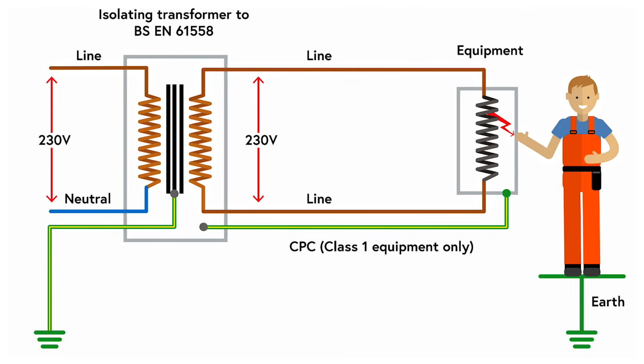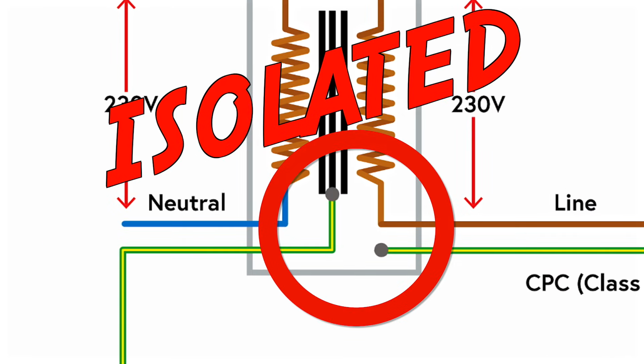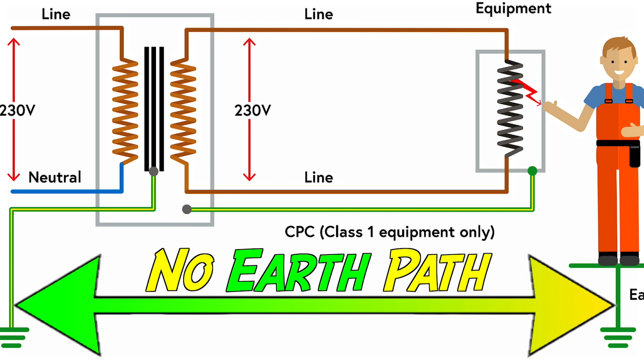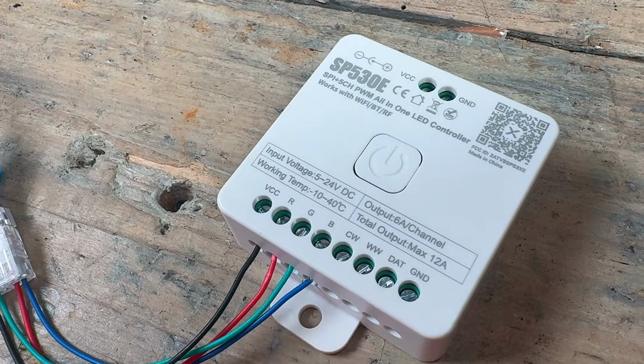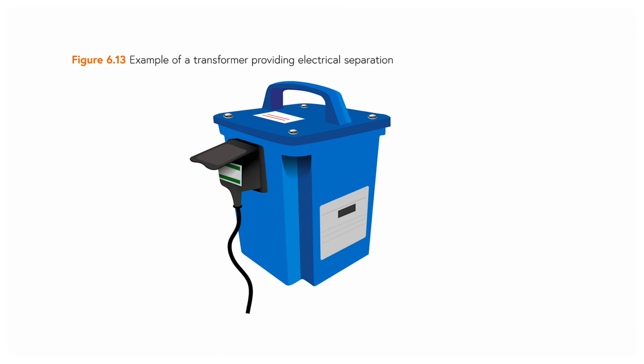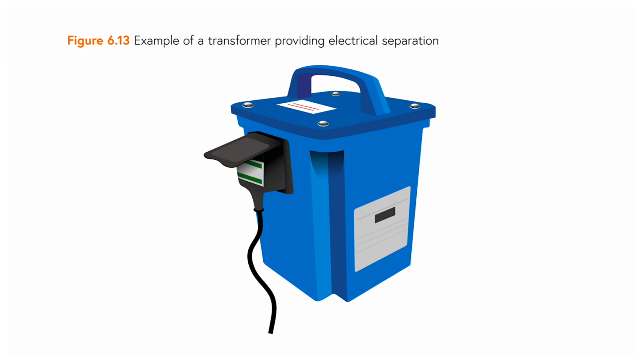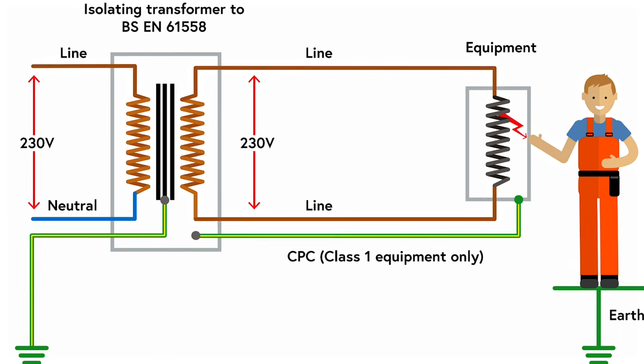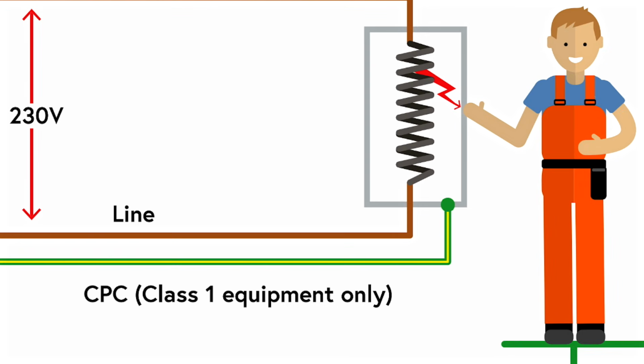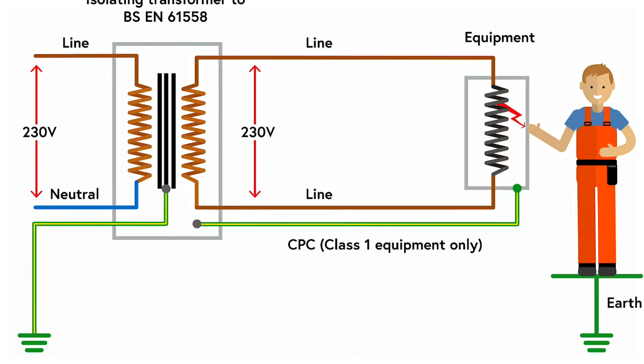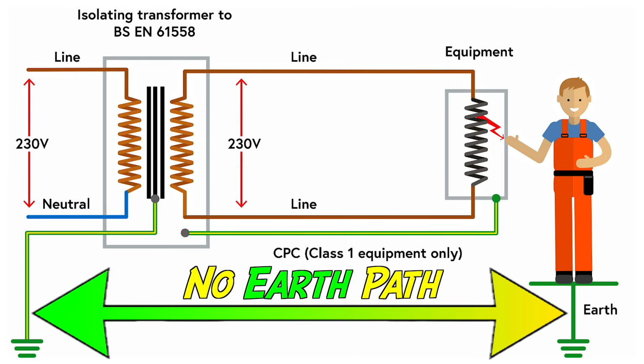Class 3 is defined by electrical separation and not voltage. The equipment is supplied from a source isolated from earth and all other live circuits. There is no intentional earth referenced on the secondary side. Many people assume Class 3 always means extra low voltage. It often does, but not always. You can have Class 3 equipment running at 230 volts through an isolating transformer. An isolating transformer has a separate primary and secondary winding with reinforced insulation between the windings. If you touched a live part on the secondary side of the transformer, you wouldn't receive a shock. Phew. Even if you were standing on the greater mass of earth, because no current can flow.